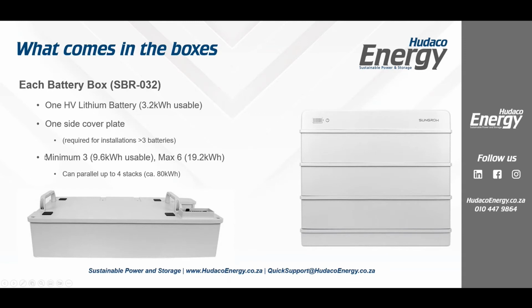We have a minimum of 3 that we stack, and we can go up to 6 in a single stack, and then we can parallel up to 4 stacks if you needed to. So to date, we've only had people go up to 2 stacks in parallel as the maximum, but you could go up to 4 stacks if you really wanted 80 kilowatt hours. I can only imagine that for somebody that would be running in a microgrid mode, maybe in a fairly remote area, that they would then want to go that big.